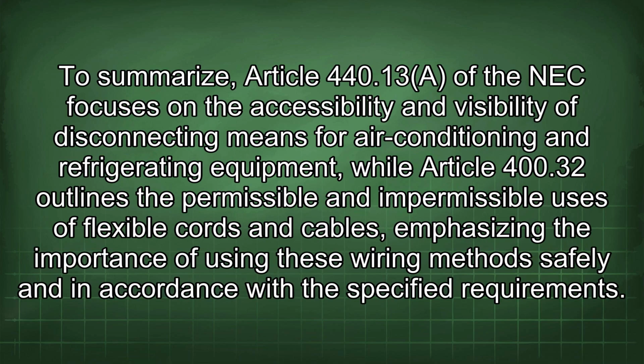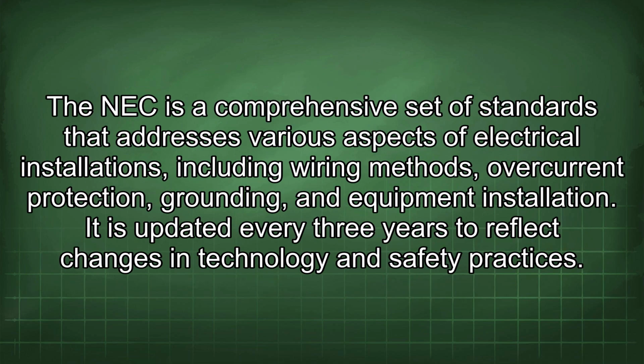To summarize, Article 440.13 of the NEC focuses on the accessibility and visibility of disconnecting means for air conditioning and refrigerating equipment, while Article 400.32 outlines the permissible and impermissible uses of flexible cords and cables, emphasizing the importance of using these wiring methods safely and in accordance with the specified requirements. The NEC is a comprehensive set of standards that addresses various aspects of electrical installations, including wiring method, overcurrent protection, grounding, and equipment installation. It is updated every 3 years to reflect changes in technology and safety practices.